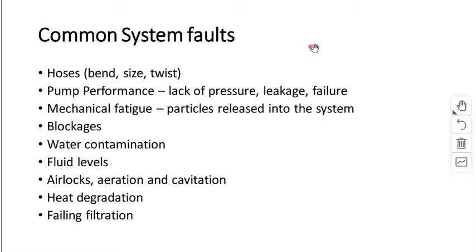Fluid levels, if they're not up to date, so simple fault, if it sucks in air and the fluid level in the tank is too low, maybe there's been a repair, nobody noticed it, and suddenly the system starts behaving erratically. It could be that the fluid level is low. So all you need to do is just fill up the tank with hydraulic oil.